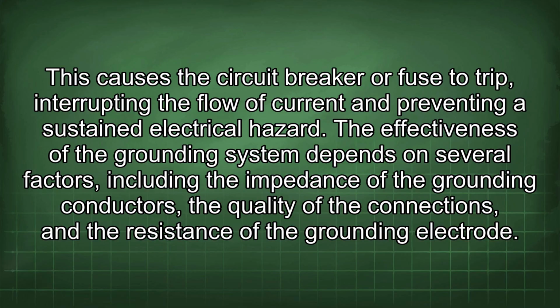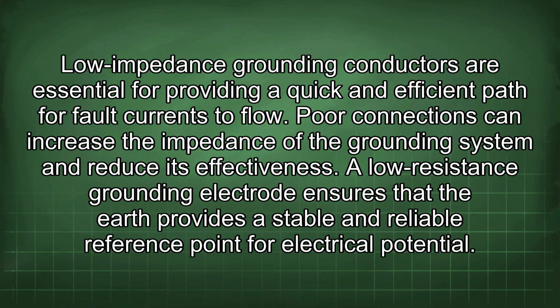The effectiveness of the grounding system depends on several factors, including the impedance of the grounding conductors, the quality of the connections, and the resistance of the grounding electrode. Low impedance grounding conductors are essential for providing a quick and efficient path for fault currents to flow. Poor connections can increase the impedance of the grounding system and reduce its effectiveness. A low resistance grounding electrode ensures that the earth provides a stable and reliable reference point for electrical potential.